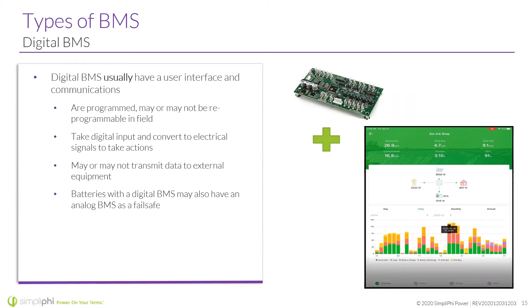Just wanted to point out that batteries with a digital BMS, that doesn't mean they don't also have an analog BMS. They could have both. For example, you could set your digital BMS to execute a high voltage disconnect at 58 volts, and you may even have an analog BMS back there as a failsafe to execute a high voltage disconnect at 60 volts, in case the digital BMS for whatever reason fails.